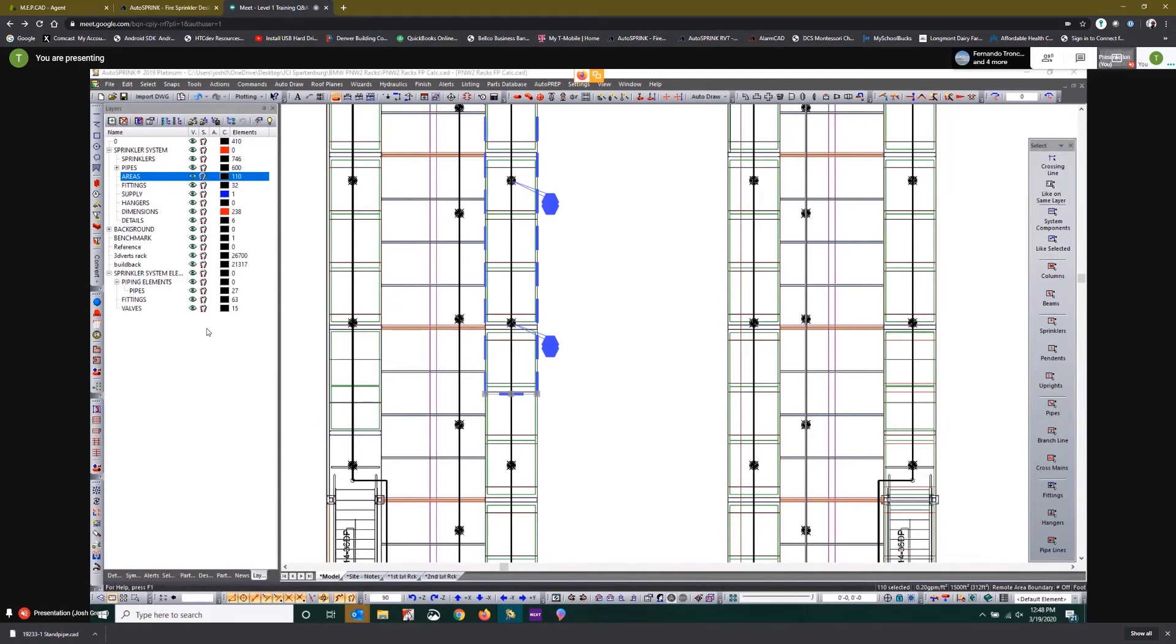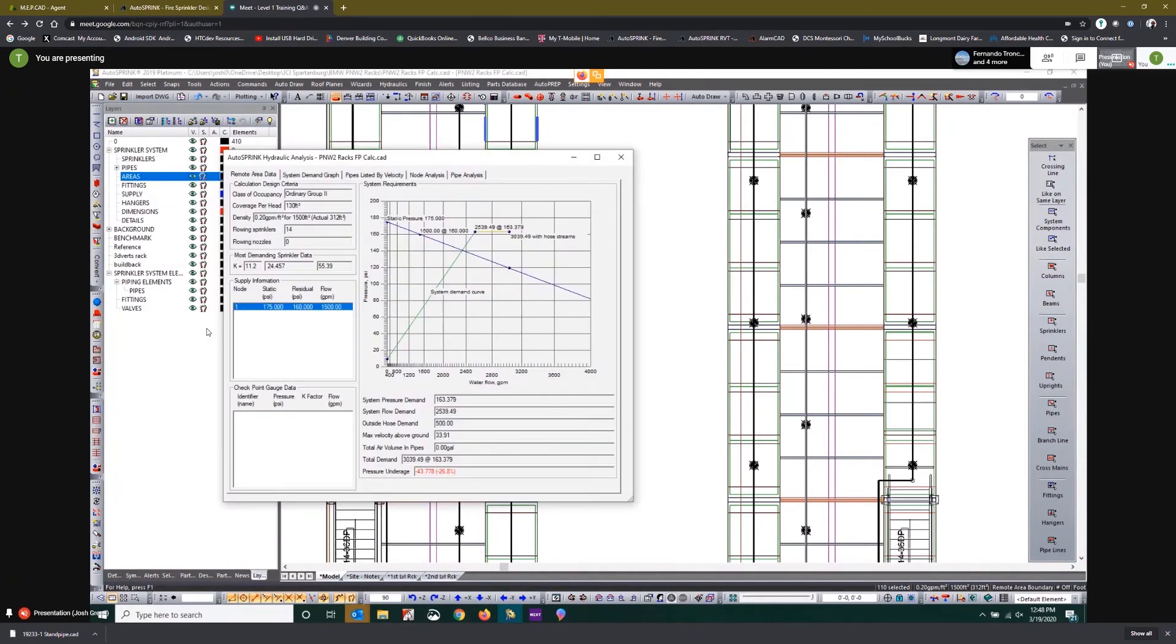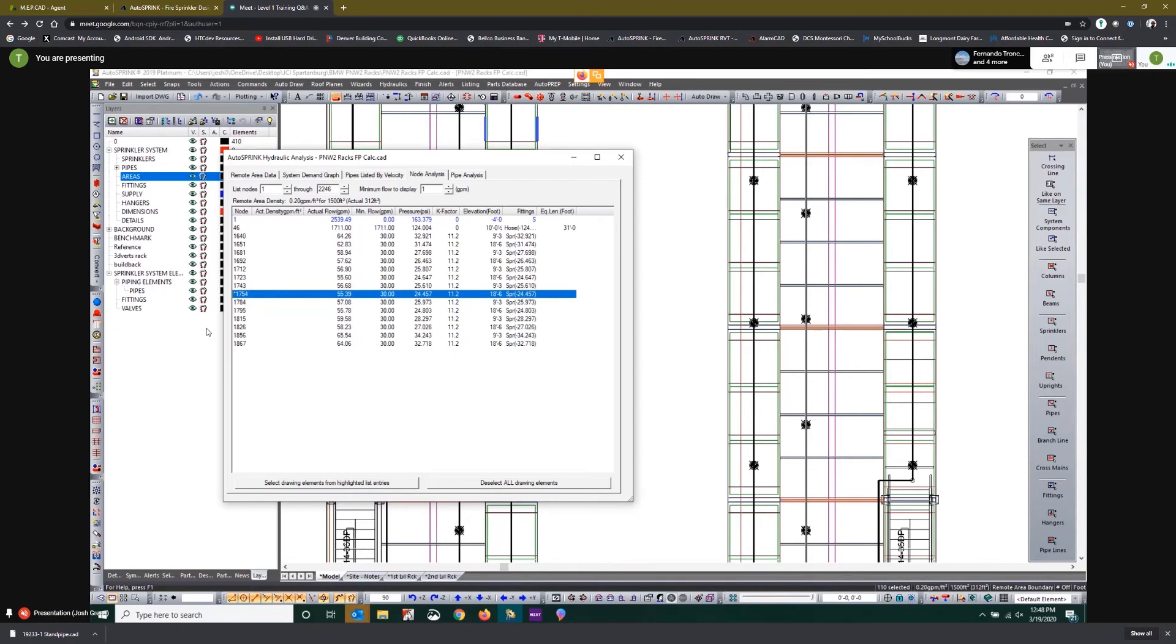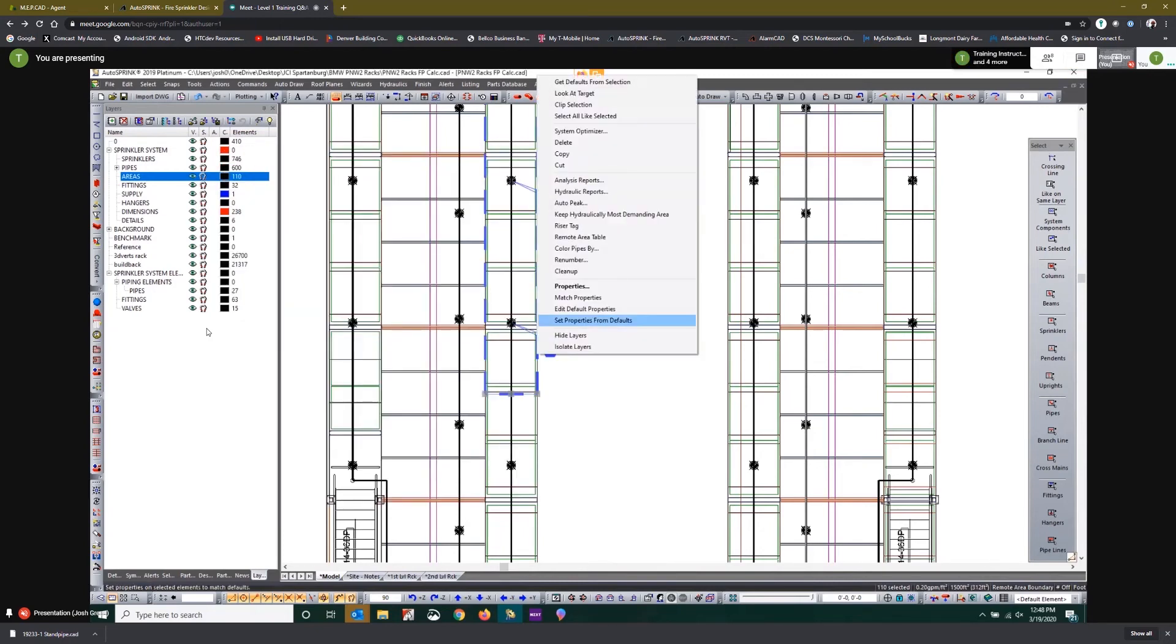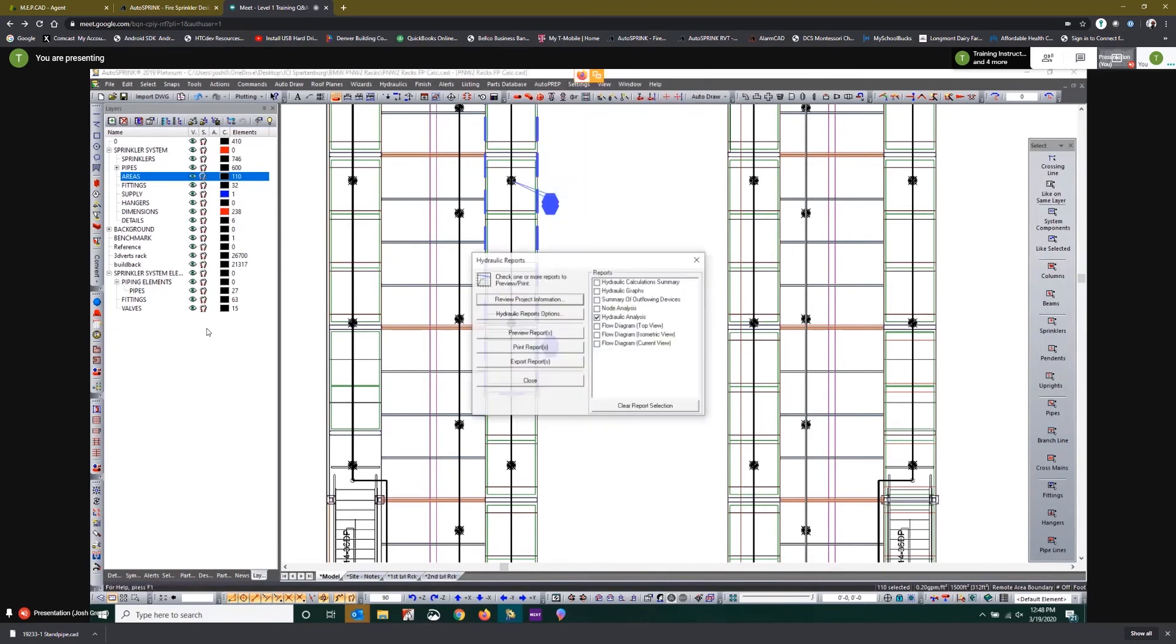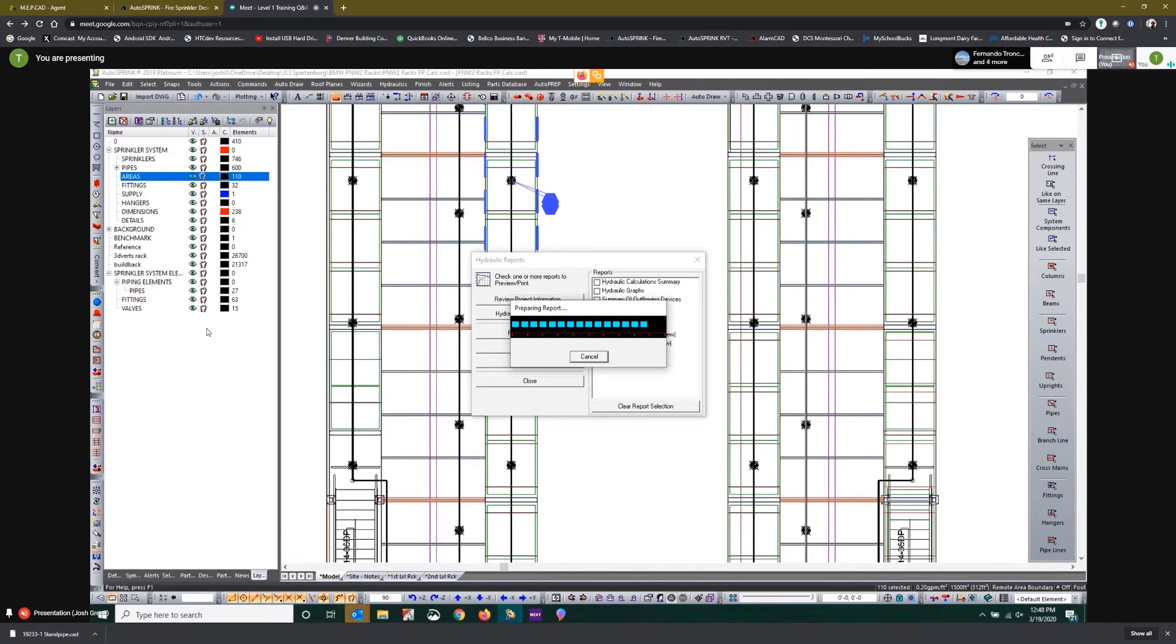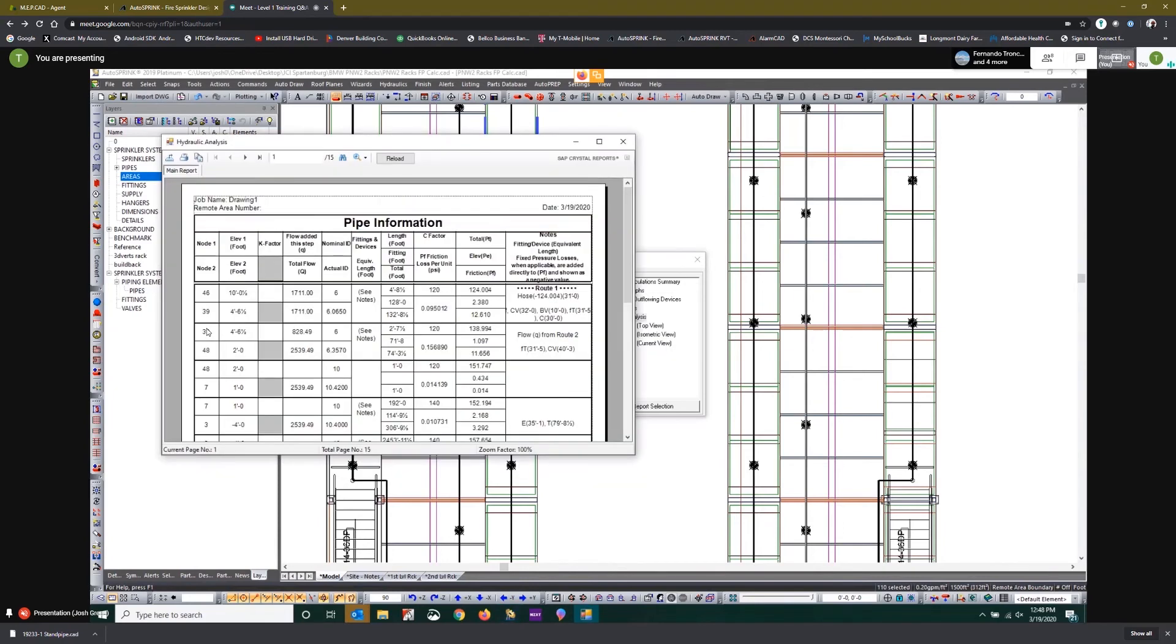Okay, so let's take a look at the node analysis tab because I don't know what's driving the demand of the system. It's saying that sprinkler 1754 is the most demanding sprinkler, but that doesn't necessarily mean that that's what's driving the system. The hose valve might actually be driving the system. So if we right click on the remote area and select hydraulic reports and then preview the selected hydraulic analysis, the program will always populate the most demanding path. This starts at the hose valve, which tells us that the hose valve is driving the demand of this calculation.